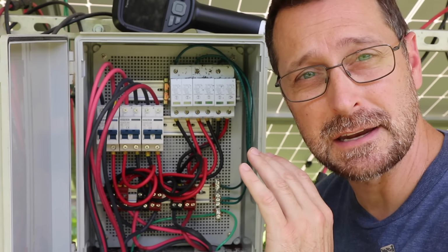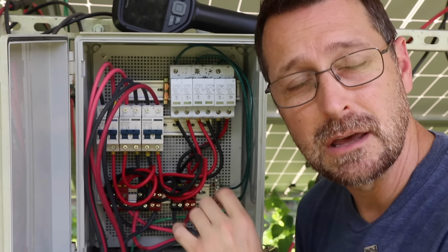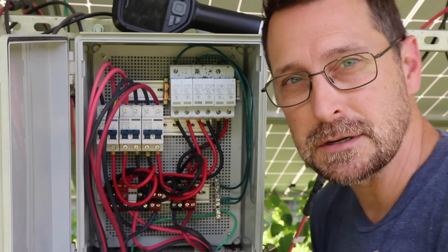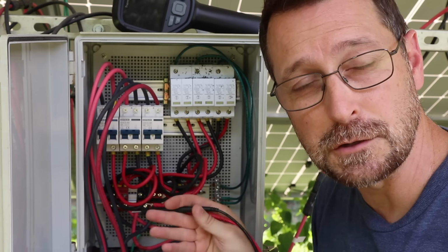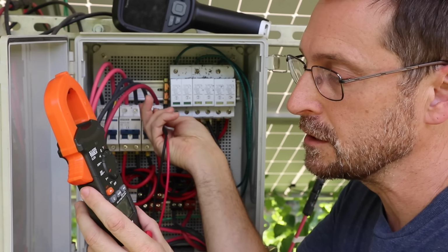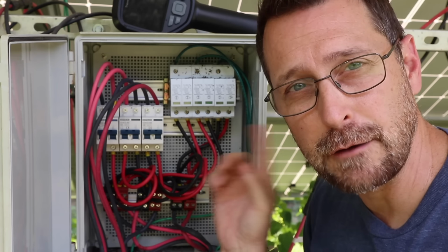Okay, we want to see if there's any connection problems in the system. So at each point of connection, you want to make sure things are tightened down properly, like all the connection points here, and that you are getting consistent voltage through it. So we go to the top of our string right here and we look at the voltage, 219 volts. That is consistent with the string voltage of that front array.